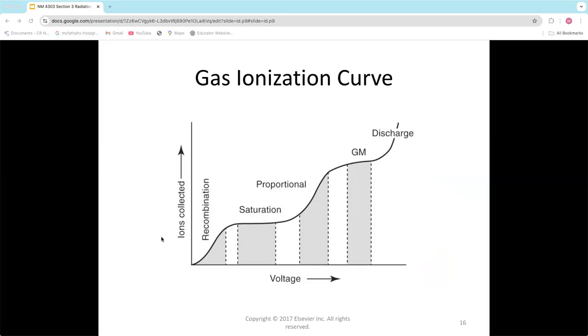So what happens in the system as radiation comes in, if our voltage is really, really low? As radiation comes in, it will strike and create that electron and ion pair. If the voltage is low, there's not enough pull to pull those things to the cathode and the anode. They will simply split from the reaction and then actually recombine. And so initially in this gas ionization curve, we have what's called the recombination region. Again, the reaction happens, they separate, but they come back together because there's not enough voltage.